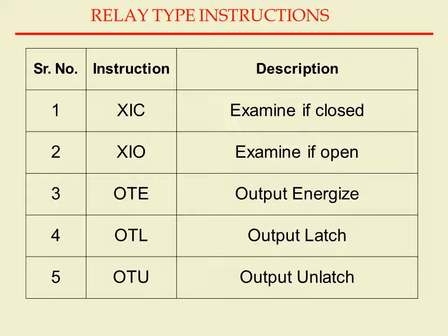The first relay instruction is XIC, which means examine if closed. Second is XIO, which means examine if open. Then OTE, that is output energize. OTL, output latch. OTU, output unlatch.